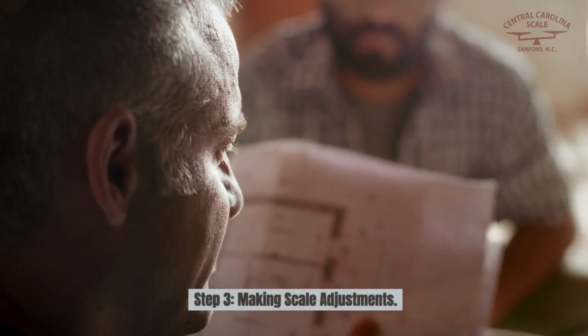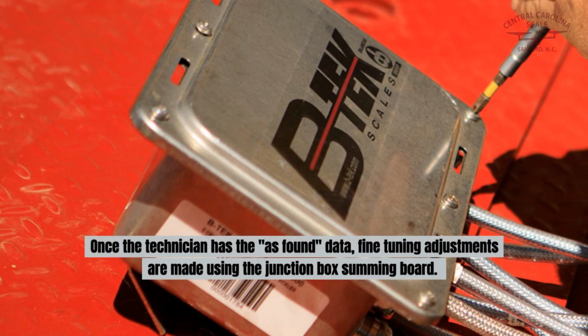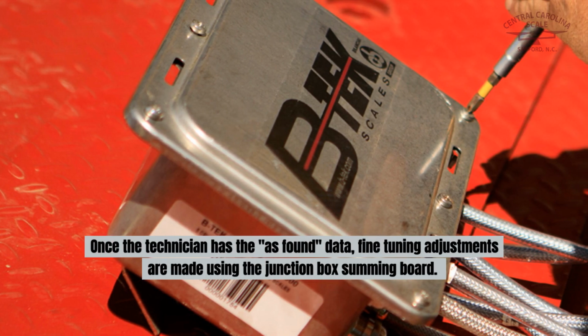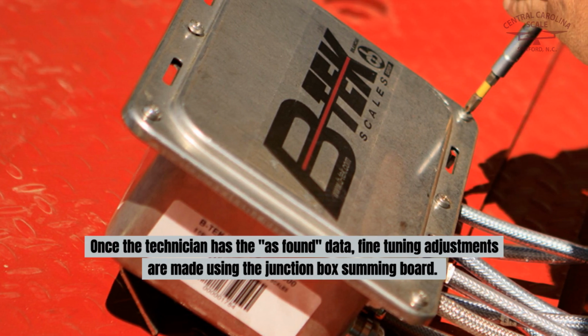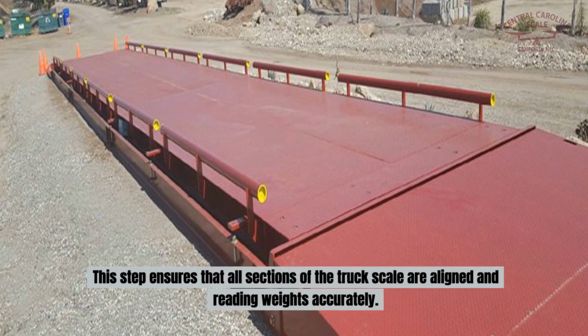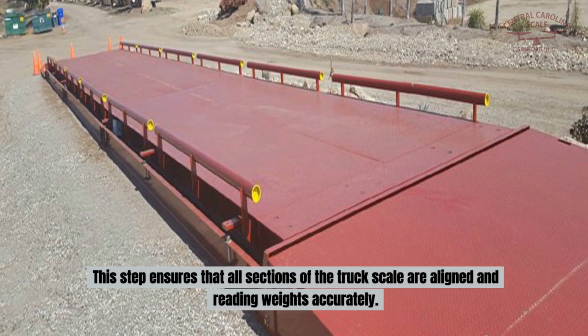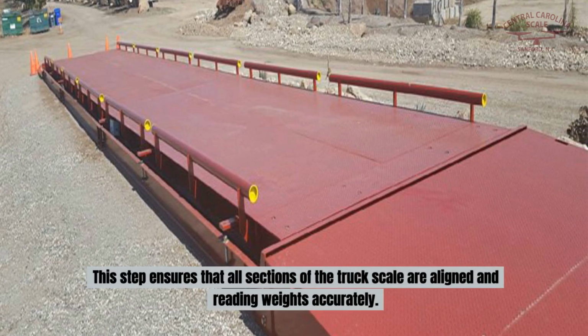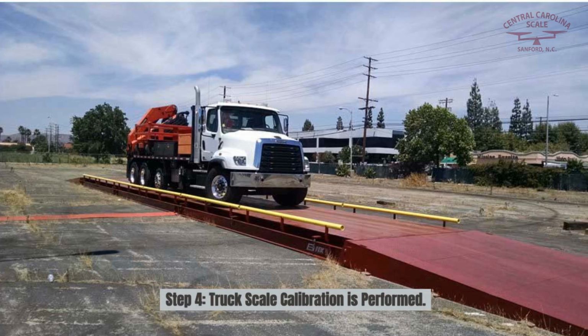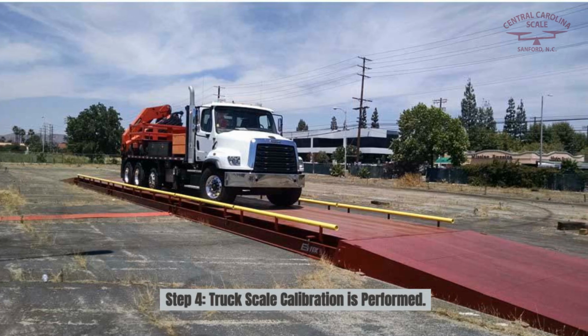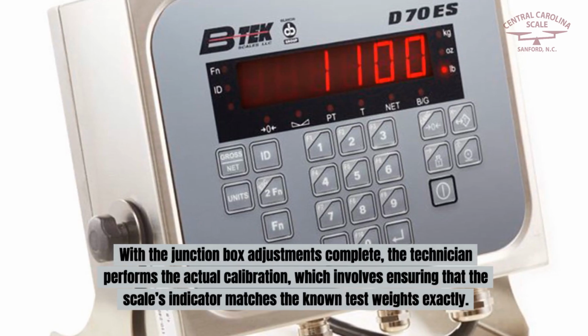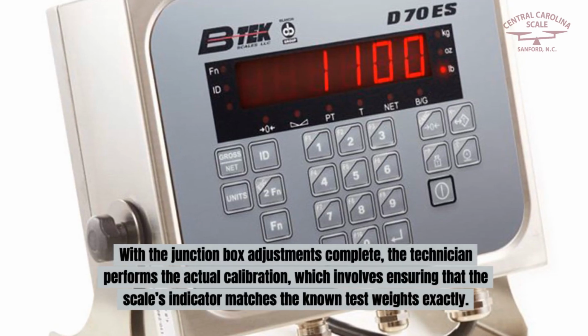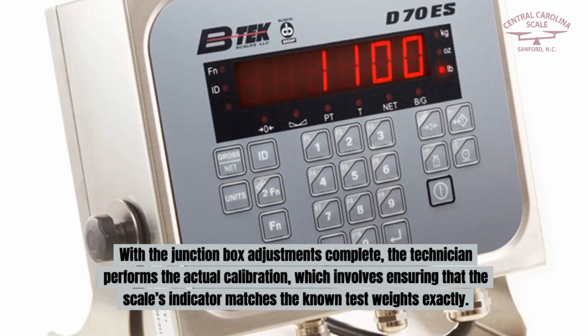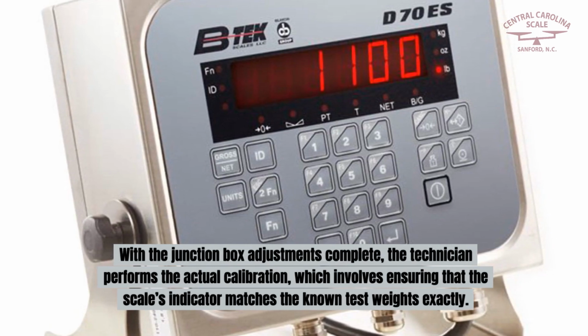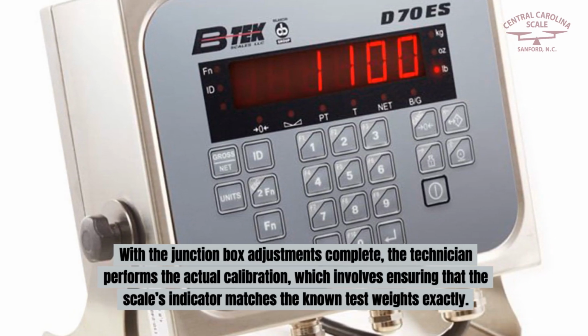Step 3. Making scale adjustments. Once the technician has the as-found data, fine-tuning adjustments are made using the junction box summing board. This step ensures that all sections of the truck scale are aligned and reading weights accurately. Step 4. Truck scale calibration is performed. With the junction box adjustments complete, the technician performs the actual calibration, which involves ensuring that the scale's indicator matches the known test weights exactly.